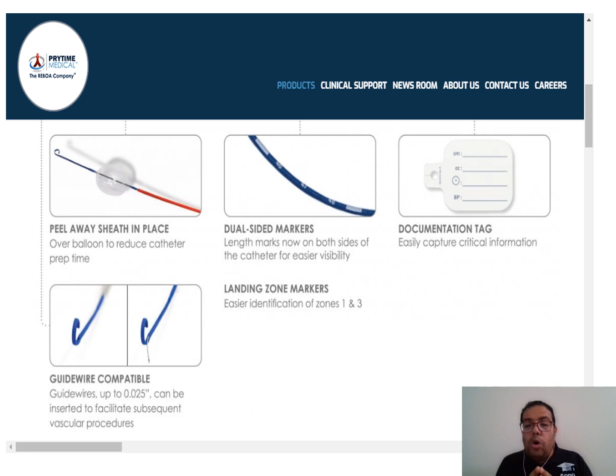Let's continue with our REBOA Plus. It has a tag for timing. It has a peel away sheath built on the balloon in order to protect it. It has more markers on the shaft of the REBOA in order to see it from both sides. It has a documentation tag. Also, it is guide wire friendly and has marks to know zone 1 and zone 3. So it is good now to know the new generation.